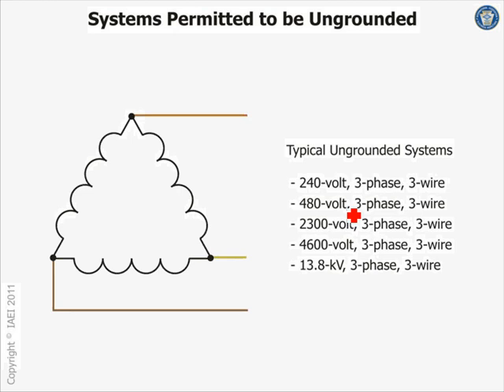A 240 three-phase system is permitted to come to a building, feed a building, or be a power source in a building ungrounded. So you can bring it to a system. But by the way, this could be a power system coming from the utility to your building, or a power system that you create and own and operate. So I can take my power system, put a transformer, delta, feed my single line that all of them are running at 240 three-phase, 480. So these are the two most important ungrounded systems in the low voltage business that we use.